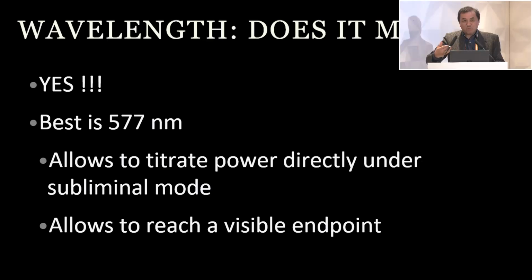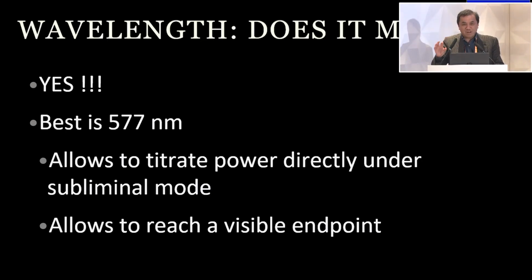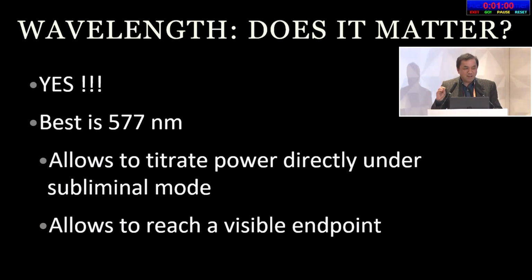And in the past, when we had the 810 nanometer laser, for instance, it was not possible to really titrate power directly in the micropulse mode. You had to do it under conventional photocoagulation mode, and sometimes accidents occur because you chose the power, but you forgot to switch back to the micropulse mode, and you're treating in the macula, and you go, oops, and that can be a problem.